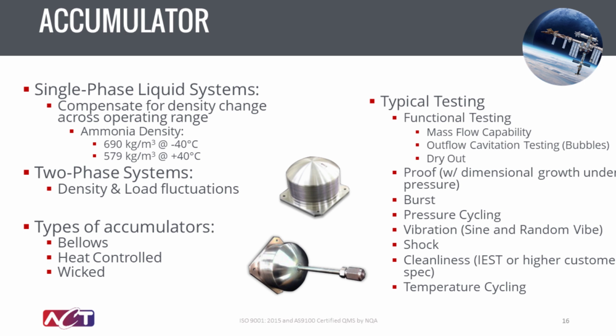And once you have the heat collection and transport mechanisms and the radiator systems designed in, the other area to take really strong consideration is the accumulator side. As we noted here, the big principle is to compensate for the density change. As an example, you can see the difference in density of ammonia between a plus 40 degrees C and minus 40 degrees C setting. So there is a fair amount of volume change associated with these fluids as they collect heat and transfer heat long distances. So you have to be able to compensate for that in your system, and accumulator technology is a really necessary way, but it has also gone through a lot of fairly elaborate design cycles, so it is a pretty reliable technology at this state.